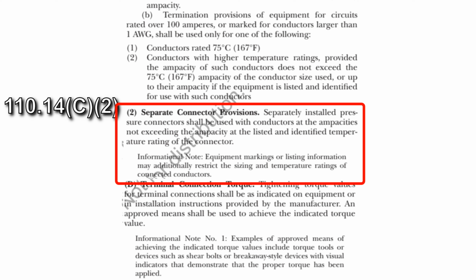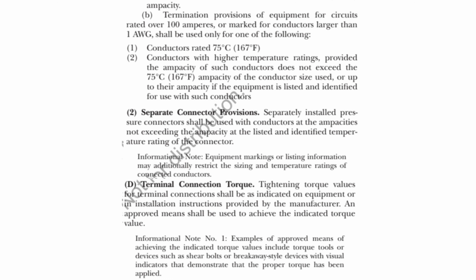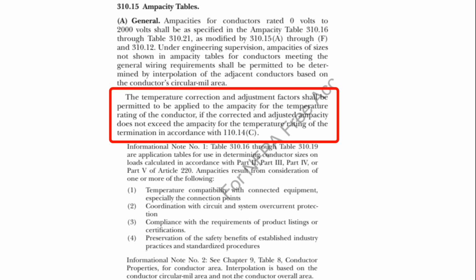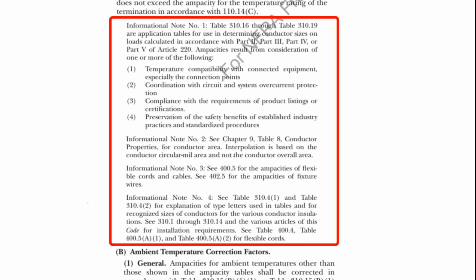But wait, there's more. 110.14(C)(2), separate connector provisions. Separately installed pressure connectors shall be used with conductors at the ampacities not exceeding the ampacity at the listed and identified temperature rating of the connector. So temperature ratings really apply to every device we use to make a conductor connection. The informational note indicates that markings or listing information may additionally restrict the sizing and temperature ratings of conductor connectors. Now let's get back to 310.15. Okay, we jumped from this statement on termination temperature settings to 110.14(C). There are some informational notes just below that you can review on your own. Those will just bog this video down.